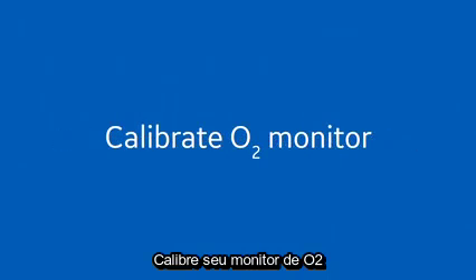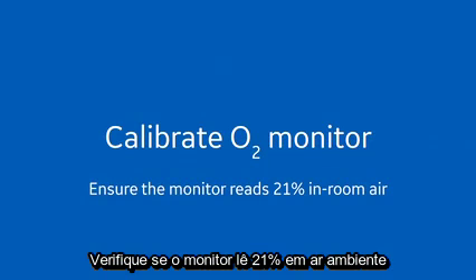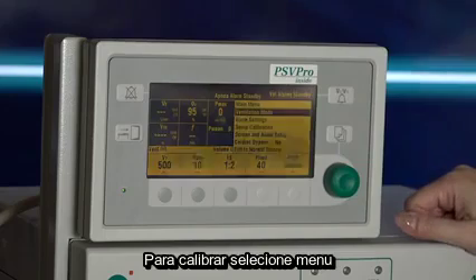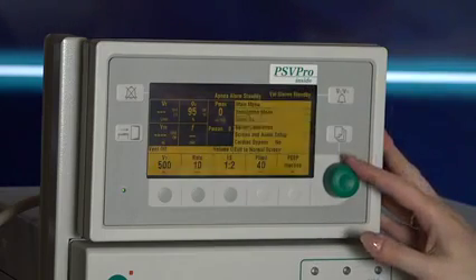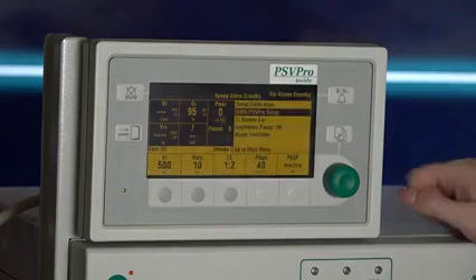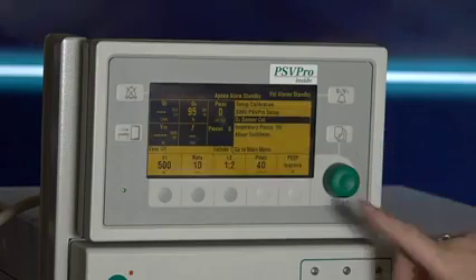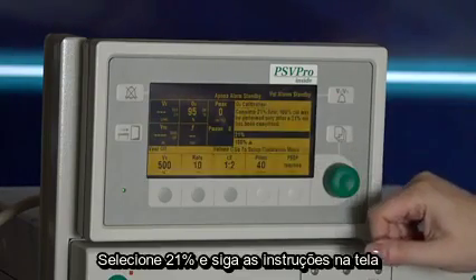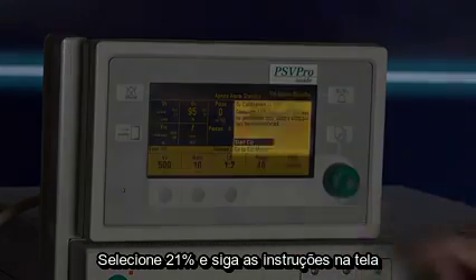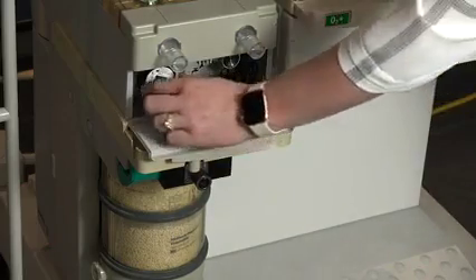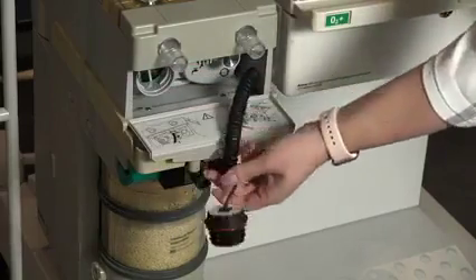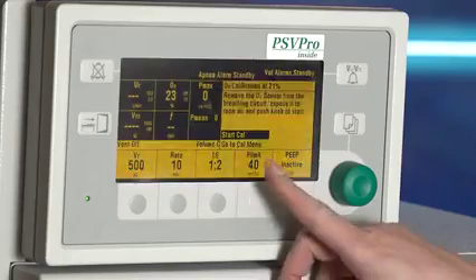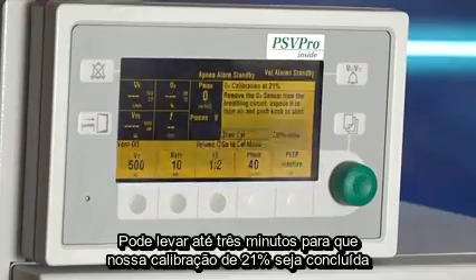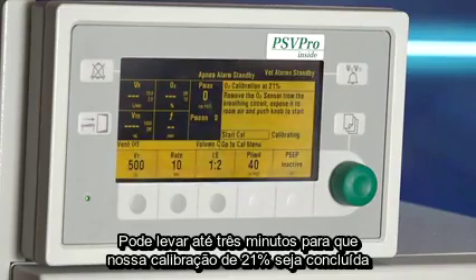Calibrate your O2 monitor. Ensure the monitor reads 21% in room air. To calibrate, select Menu, scroll to Calibration, select O2 sensor. Select 21% and follow the on-screen instructions. Select Start Calibration. It can take up to 3 minutes for a 21% calibration to complete.